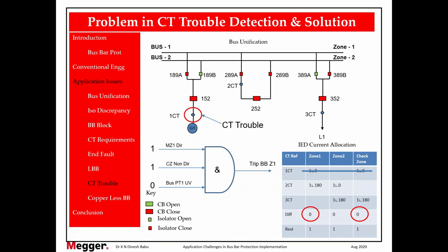Just assume another condition. If main zone directional has not picked up and many bays are there, and for this CT trouble condition, another fault occurs, then what will happen? The main zone directional will pick up. The bus PT under voltage will become high due to the fault, and the check zone is already in picked up condition, so the bus bar will trip. So in this way, for CT trouble, we should only give an alarm to the operator and we should not block the bus bar.